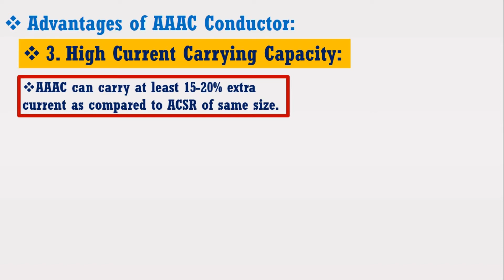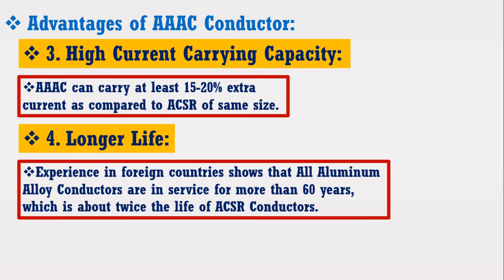Number 4. Longer life. Experience in foreign countries shows that all aluminium alloy conductors are in service for more than 60 years, which is about twice the life of ACSR conductors. Number 5. Thermal stability. All aluminium alloy conductors are stable up to 90 degrees centigrade against ACSR, which are stable up to 75 degrees centigrade.